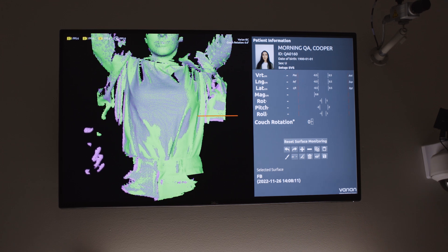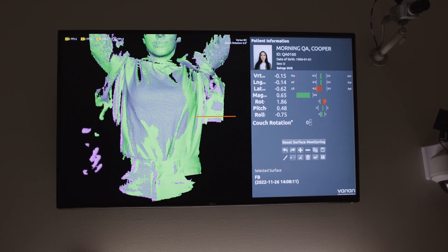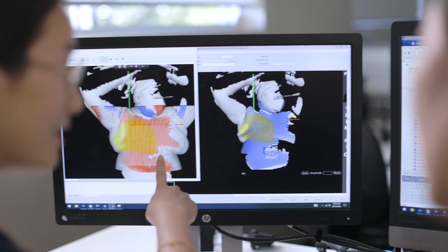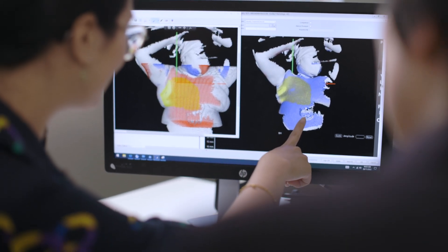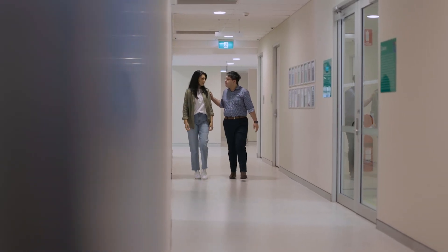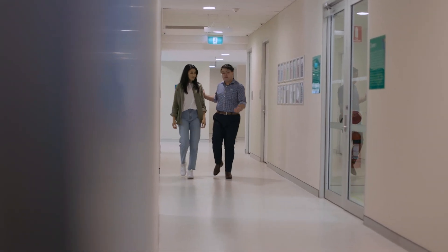Without Identify and without surface guidance, we would actually be relying on measurements and tattoos, so that may take on the order of two to three minutes more than now that we have the Identify technology. If we're able to reduce the treatment time by two to three minutes per day, that's significant.